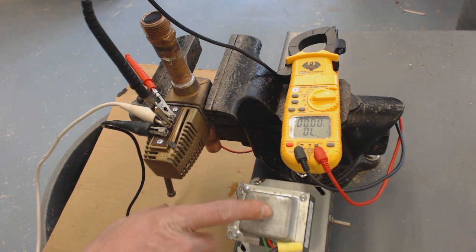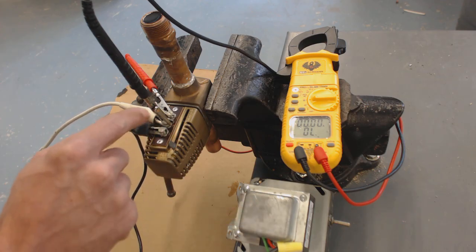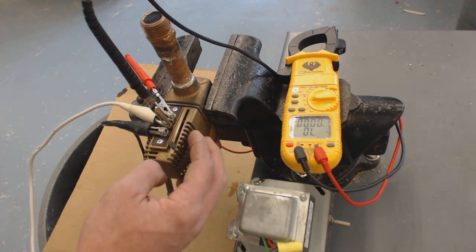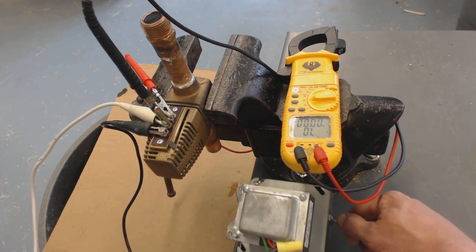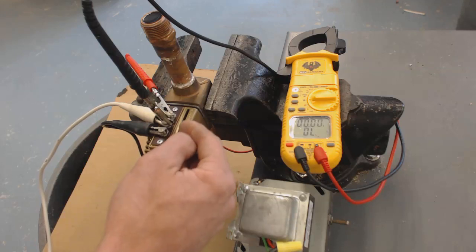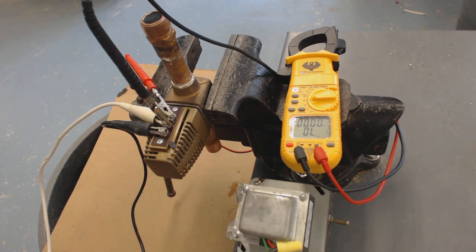We're going to turn this transformer on, power the 24 volt hot in and have the common come out. These zone valves are rated at 0.9 amps for 24 volts. We're going to turn this on. Right now we have 24 volts going from 1 through to 2 powering the heating element.